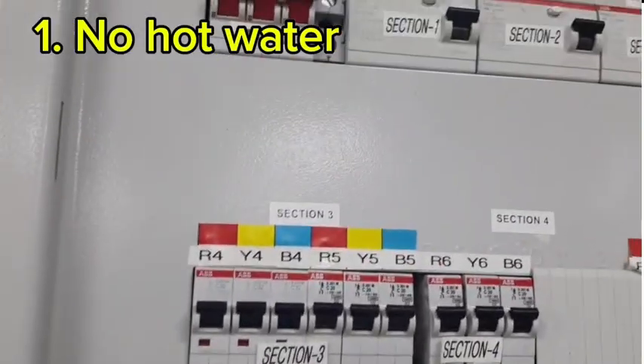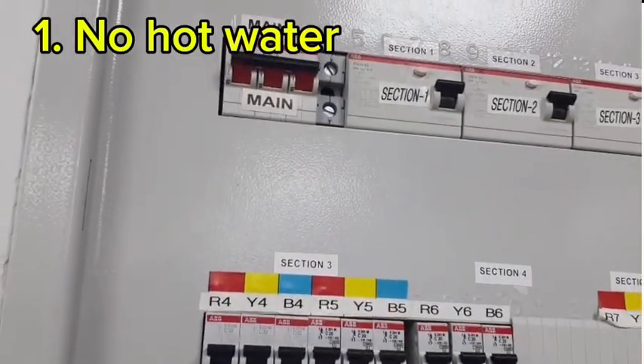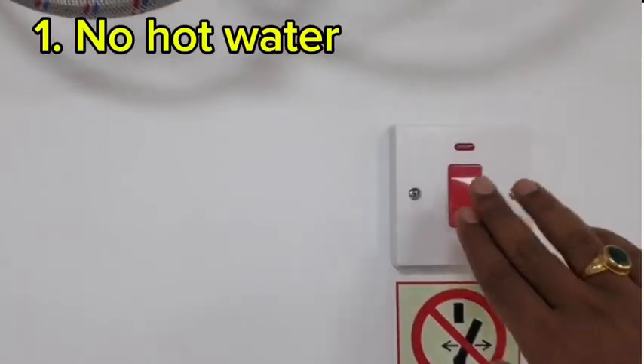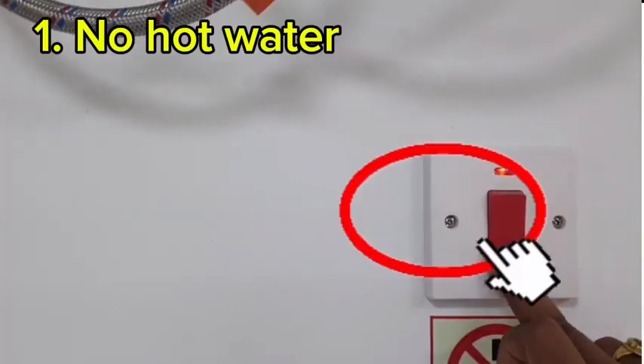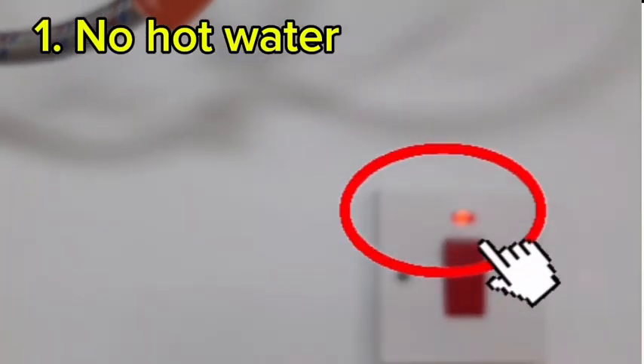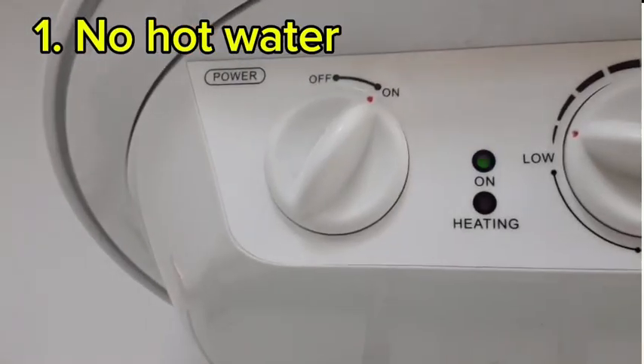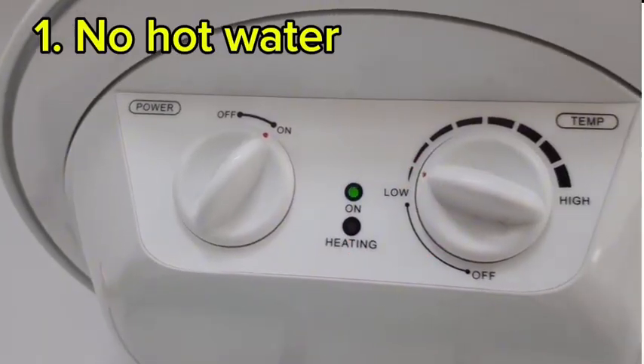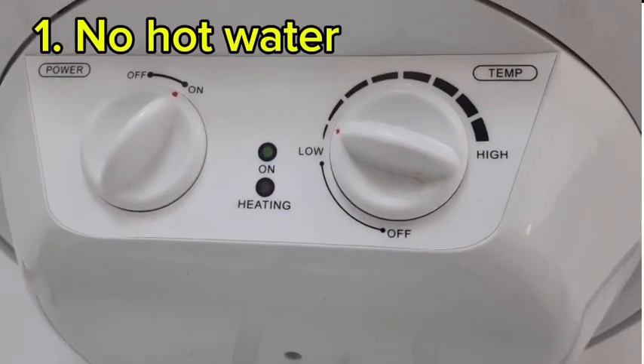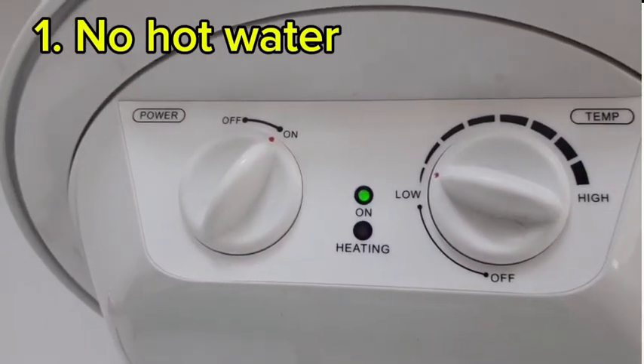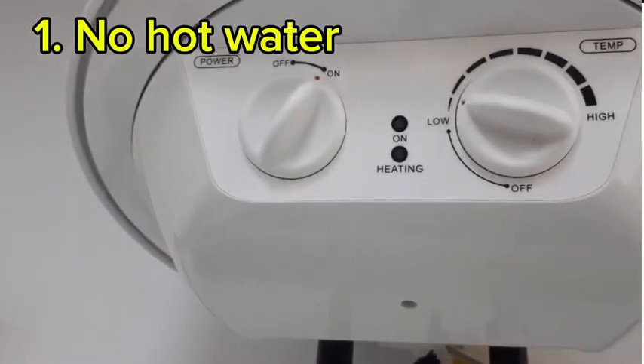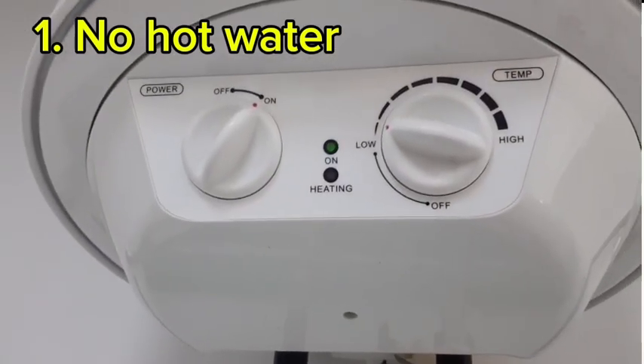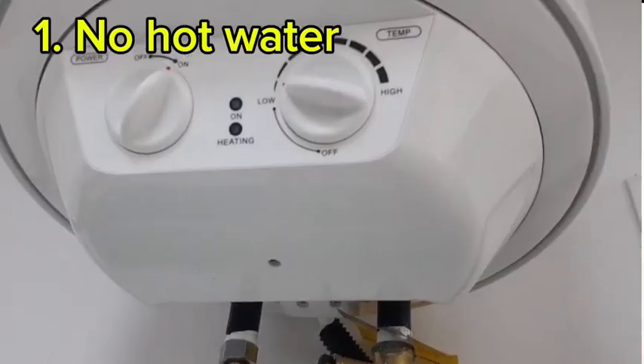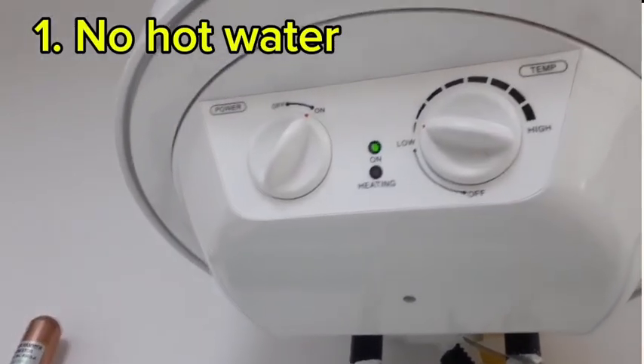So reset the breaker from here, then check the power supply in the water heater switch. Okay, you can see there is an indication, that means power is available now. Here also you can see the on indication is on. So we can adjust the regulator and the power switch is also on. If there is power supply but still there is no hot water, that means we need to check the heating element inside the water heater.